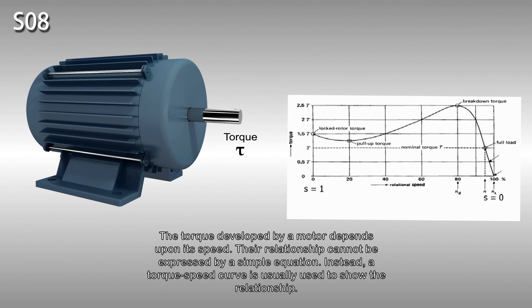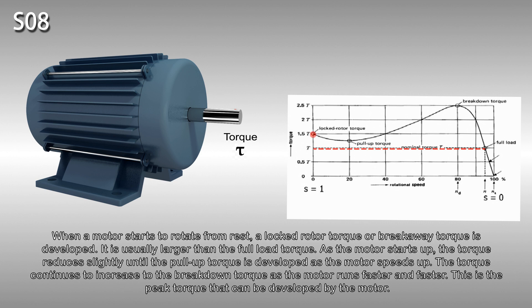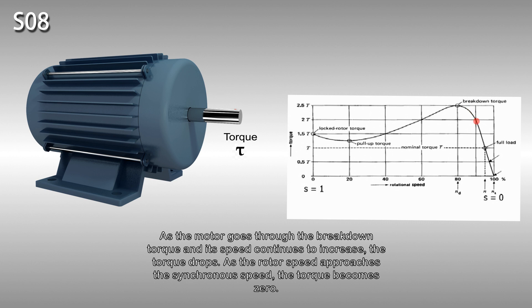The torque developed by a motor depends upon its speed. Their relationship cannot be expressed by a simple equation. Instead, a torque speed curve is usually used to show the relationship. When a motor starts to rotate from rest, a locked rotor torque, or breakaway torque, is developed. It is usually larger than the full load torque. As the motor starts up, the torque reduces slightly until the pull-up torque is developed as the motor speeds up. The torque continues to increase to the breakdown torque as the motor runs faster and faster. This is the peak torque that can be developed by the motor. As the motor goes through the breakdown torque and its speed continues to increase, the torque drops. As the rotor speed approaches the synchronous speed, the torque becomes zero.